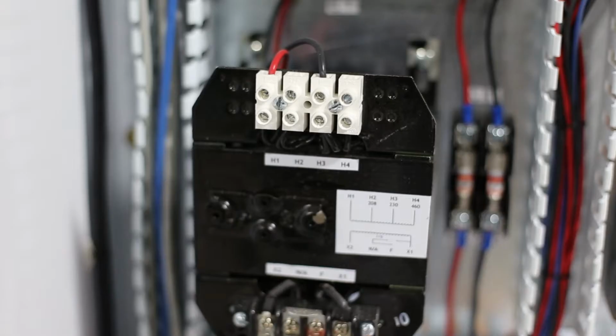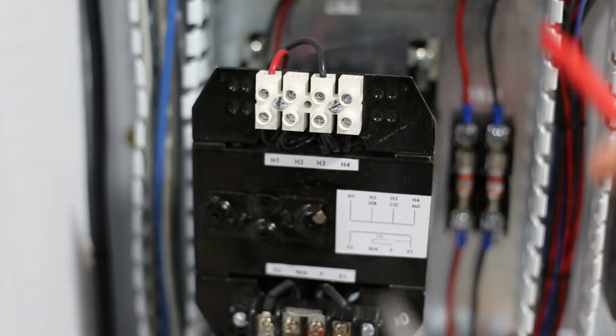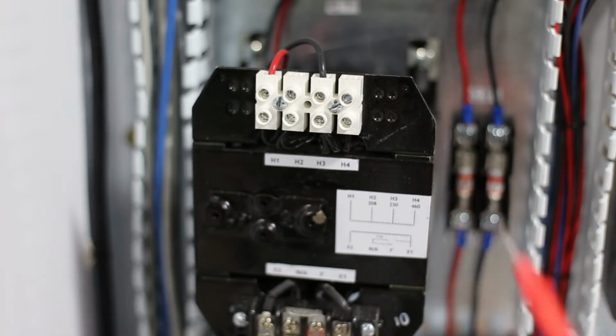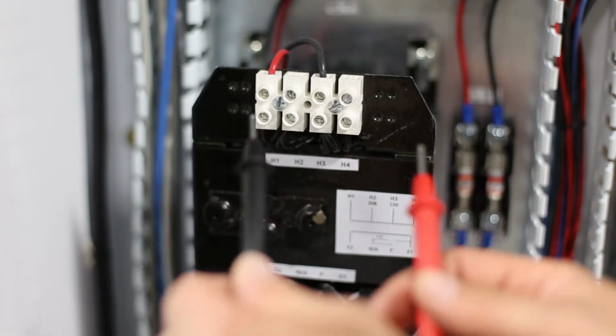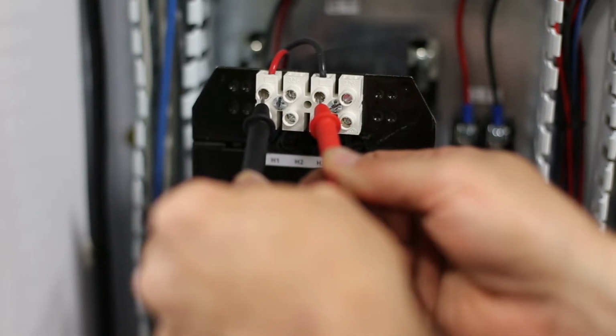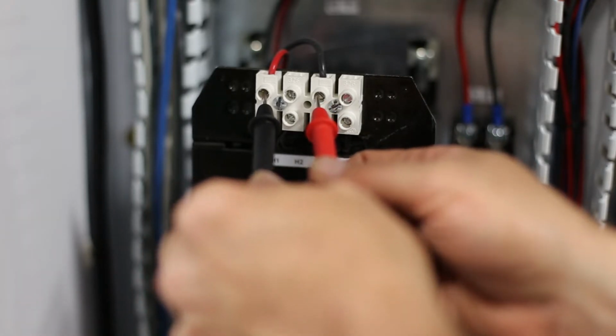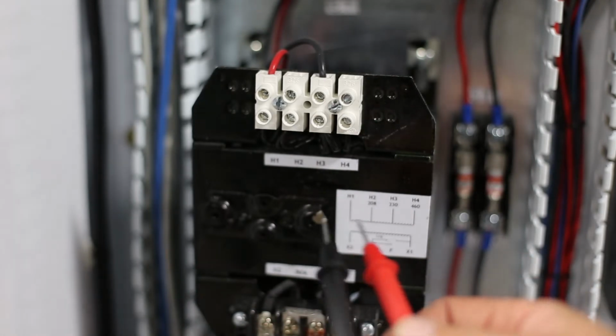If we don't have any lights, we want to know if we have power to the top side of the control transformer, or the primary side. You're going to be checking AC voltage. This is going to be either 208, 230, or 460 based on your specs at your plant. So if we check between H1 and H3 in this case here, you should have 230 volts. We have about 240 here. So that means that is good. We got power coming into our transformer.